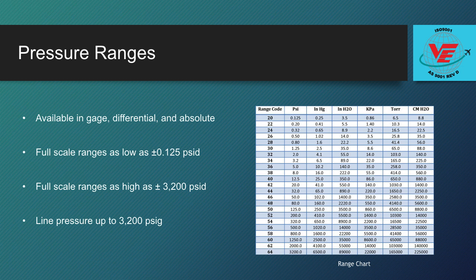The P55 is also available in pressure ranges as high as 3,200 psi, and these can be used to measure typical hydraulic pressures. Altogether, there are 23 different full-scale ranges for the P55 from 0.125 psid to 3,200 psid. In addition, every P55 can withstand line pressures of up to 3,200 psig. This means a low-range P55 can be used to measure small pressure drops in a system, even if that system is running at a high line pressure.